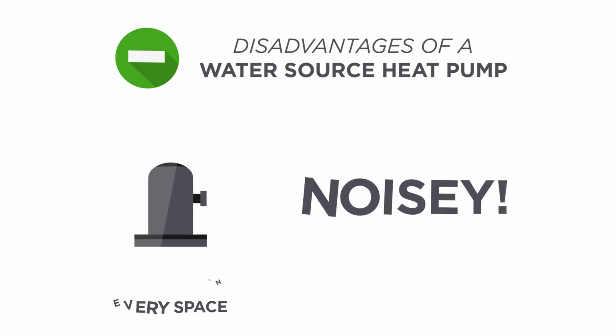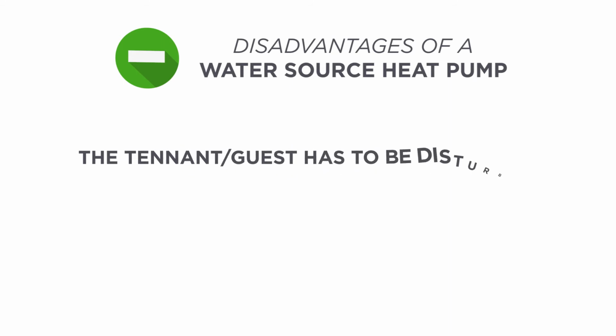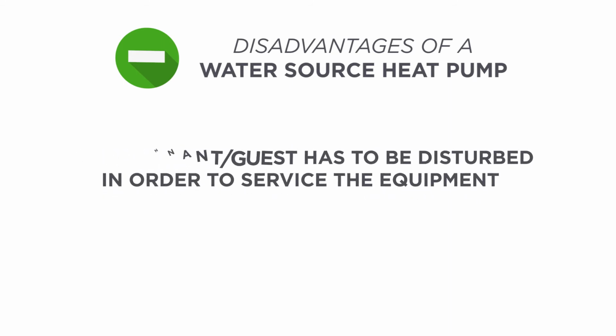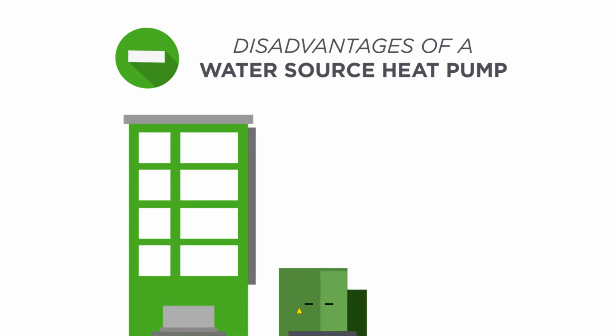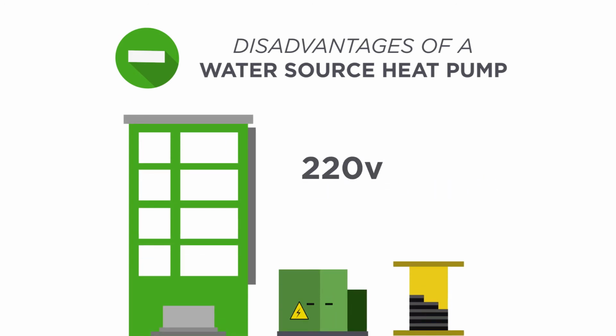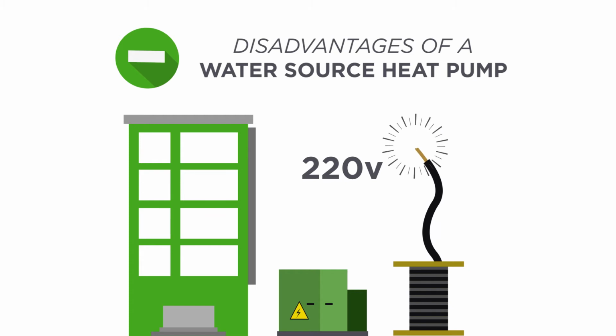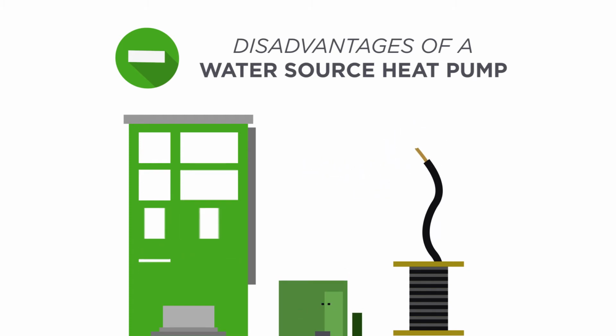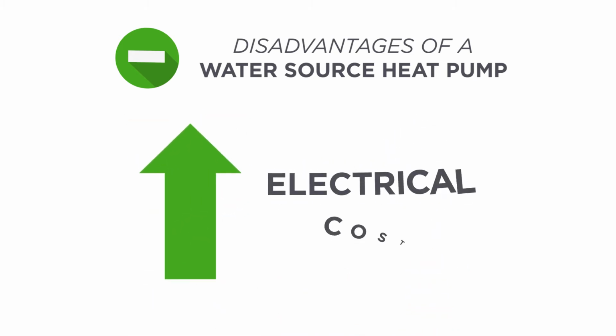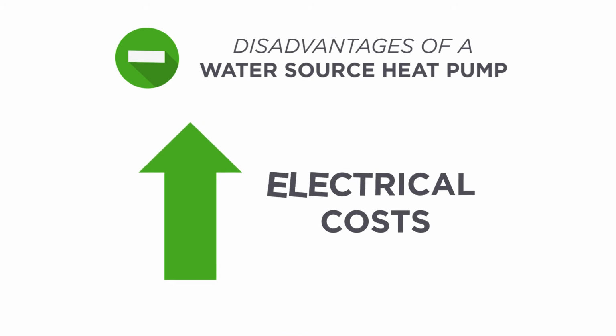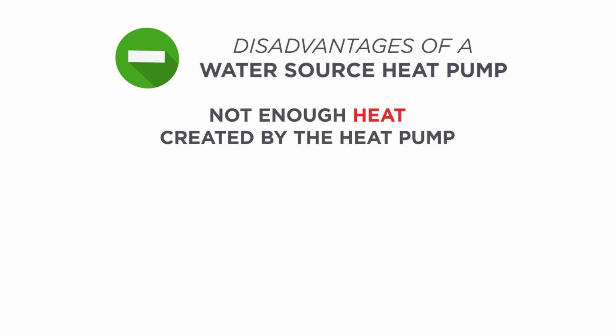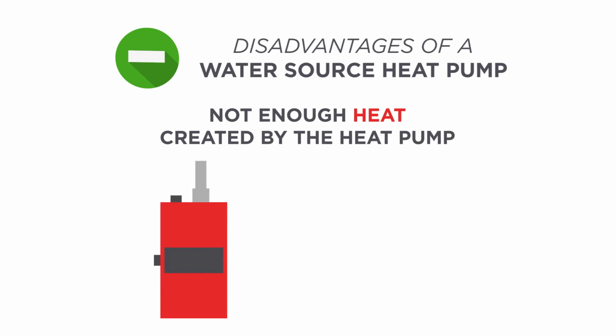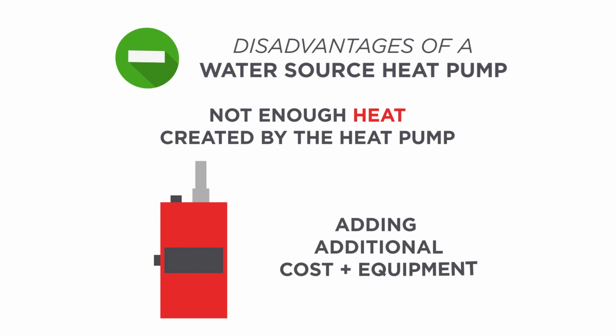In addition to the noise factor, the tenant or guest has to be disturbed in order to service the equipment. The compressor heating is electric heat, so the building transformer itself has to be increased, and 220-volt wire has to be run around the building to each heat pump to drive the compressors, increasing electrical installation costs on the project. Another major concern is there's potentially not enough heat created by the heat pump, so a secondary heating boiler is added to do what the heat pump can't do, adding additional cost and equipment.